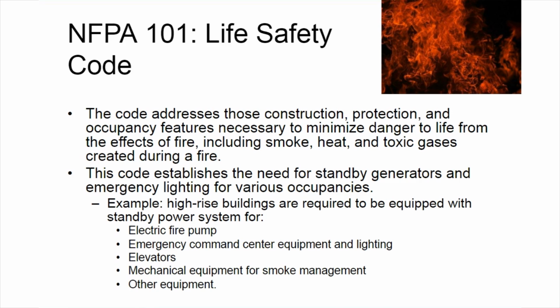As another example, NFPA 101, 7.2.3.12 requires Type 60, Class 2, Level 2 EPSS for new mechanical ventilation when required in the path of egress. So going back to 110, that means 60 seconds or less to transfer, 2 hours of runtime, and that it's a less critical load. And so you have to kind of go back and forth between the codes to understand what they're requiring.